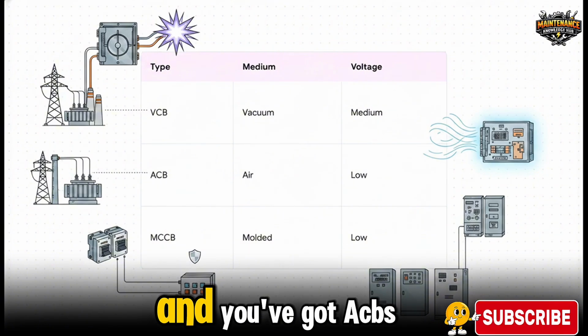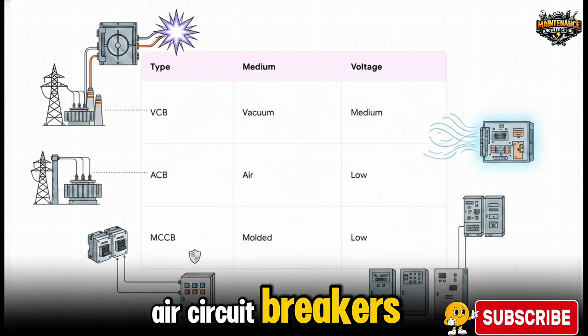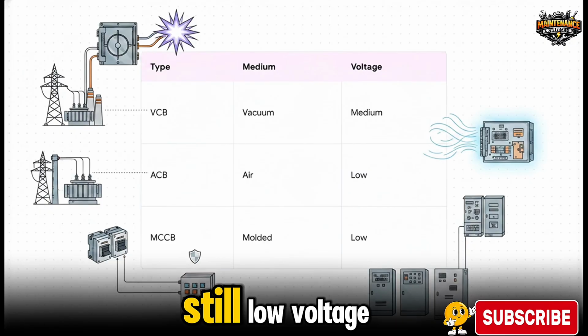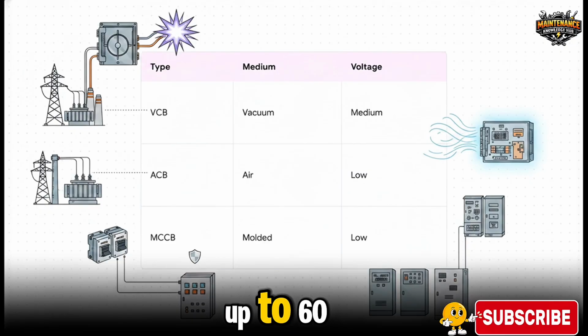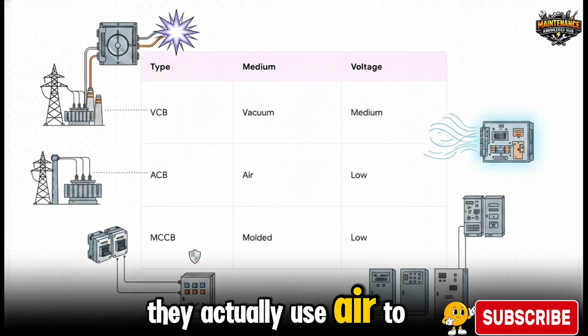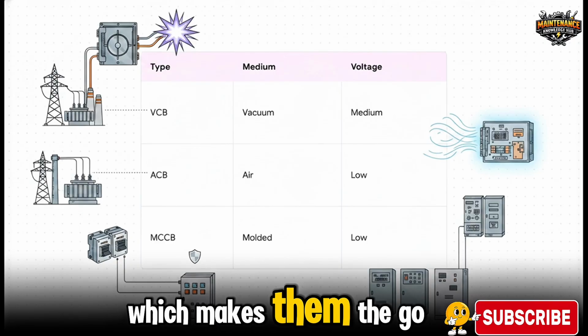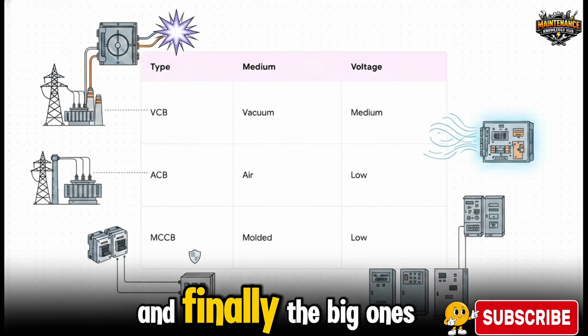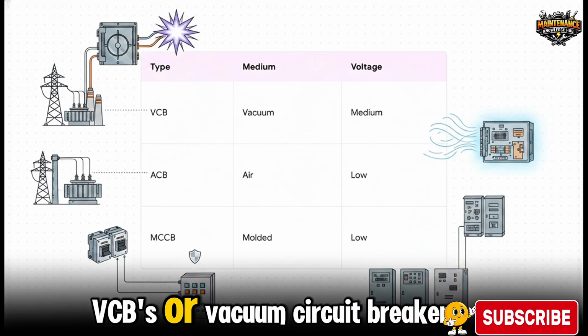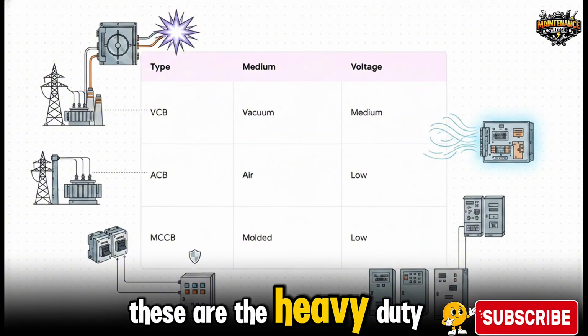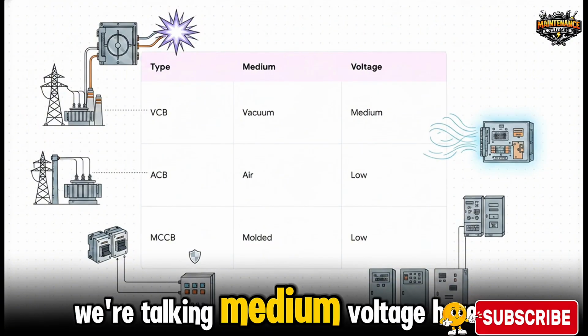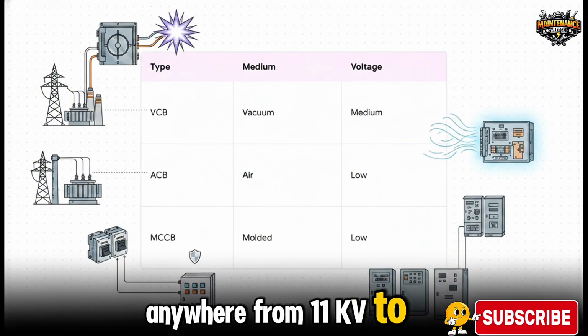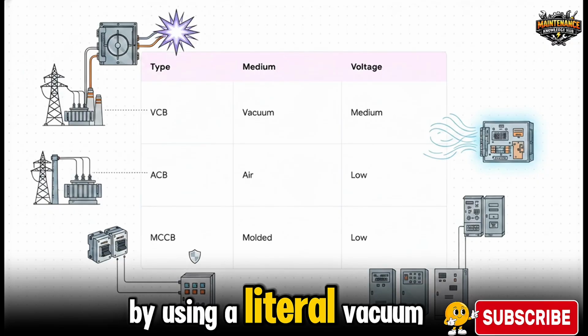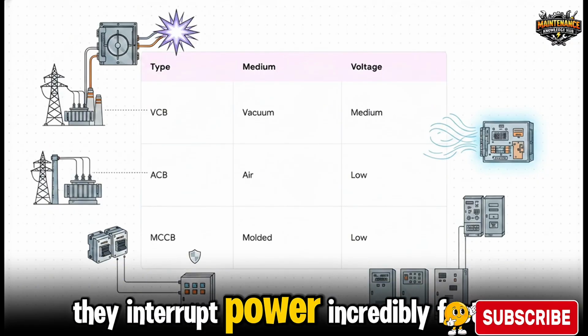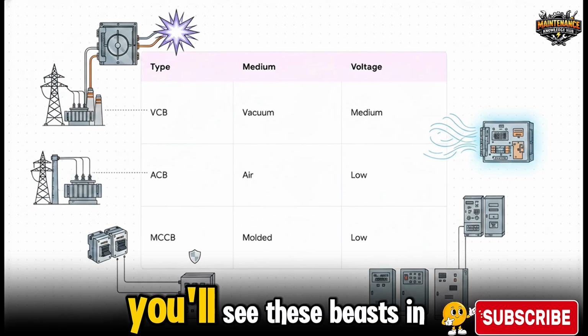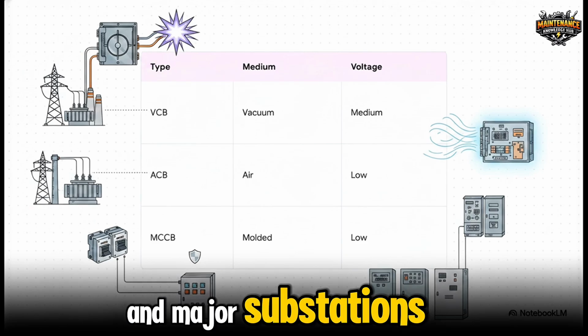Step it up a notch, and you've got ACBs, air circuit breakers. These are the high current lobby guards. Still low voltage, but they handle massive currents up to 6300 amps. They actually use air to extinguish the electrical arc, which makes them the go-to for main switchboards. And finally, the big ones, VCBs, or vacuum circuit breakers. These are the heavy-duty vault doors. We're talking medium voltage here, anywhere from 11 kV to 33 kV. By using a literal vacuum to quench the arc, they interrupt power incredibly fast and reliably. You'll see these beasts in power plants and major substations.